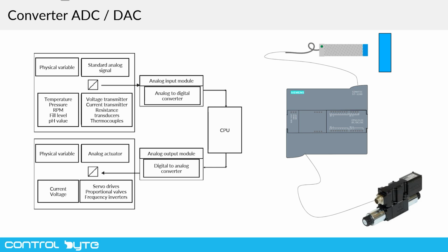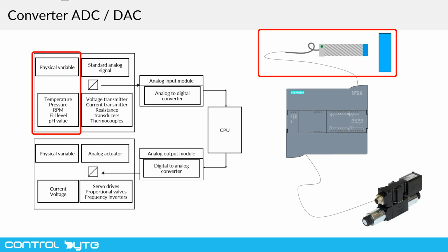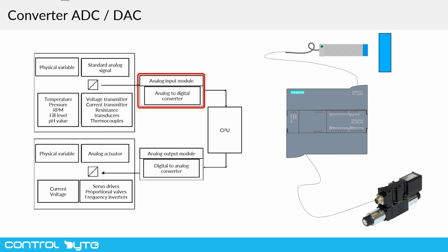This slide illustrates the signal processing flow in an automation system with sensors and actuators. Sensors measure physical variables such as temperature, pressure, RPMs, fill level, pH, and more. These values are converted into analog signals using voltage or current transmitters, resistance transducers, or thermocouples. The analog input module of the PLC then converts the signal into a digital value using an ADC for processing by the CPU.